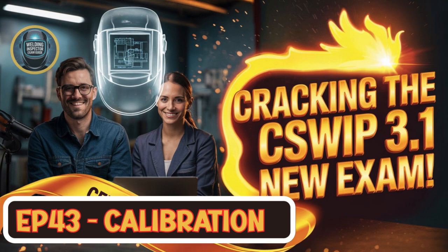There is, yeah. Our sort of guiding light here is a standard called BS EN 50504. BS EN 50504. Think of it as the code of practice. It gives clear guidance, both for the equipment manufacturers on the accuracy their meters need, the ones showing current or voltage, and for the end users, making sure those meters give reliable readings. Right, so it sets a benchmark. And within that standard, is all welding equipment treated the same, or are there different categories?